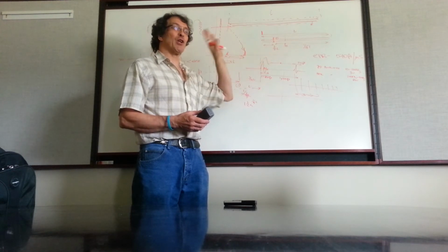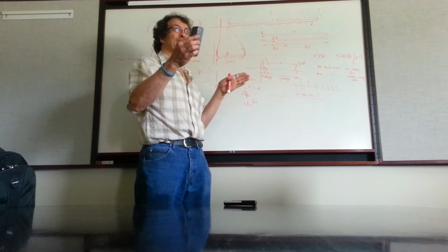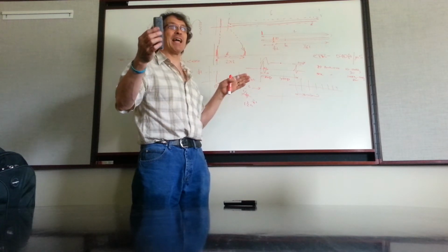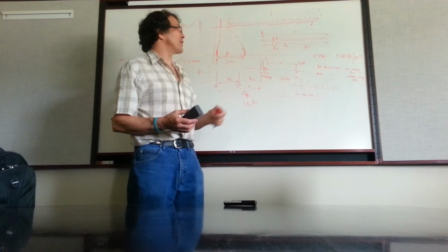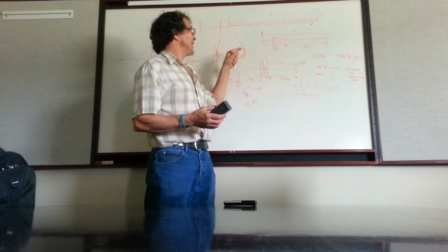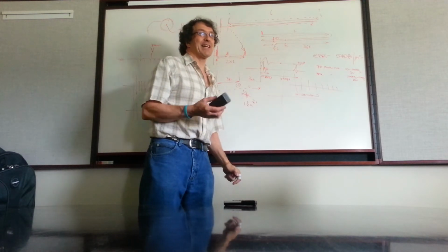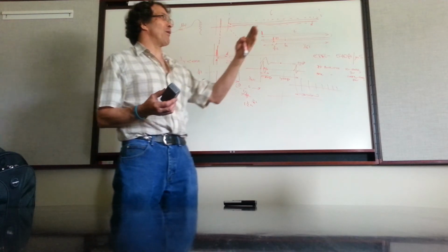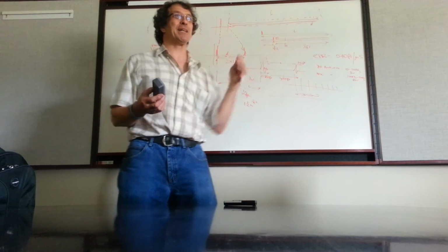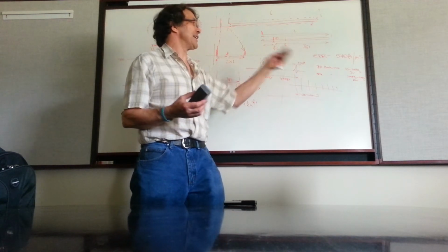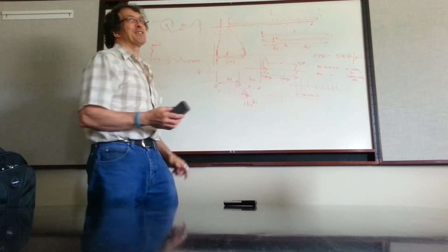Because when you look at the picture, the natural tendency is to imagine that the picture that you're seeing is a direct representation of the length of the cable, and it's not. That's right. Because the second pulse is not coming towards you. It's gone backwards first. And that's the thing that catches you out. Because you imagine, oh, I get a pulse that comes to me, and then I get another pulse that comes to me, and they're travelling down the cable, so obviously it's an exact representation. But it isn't.